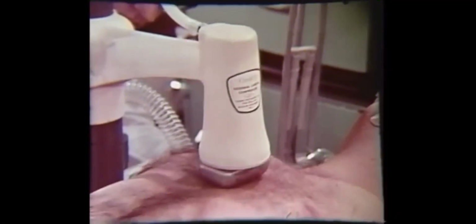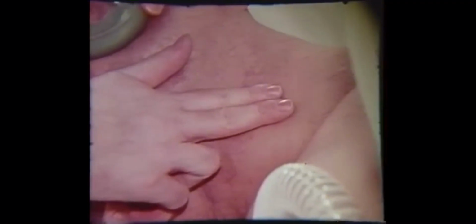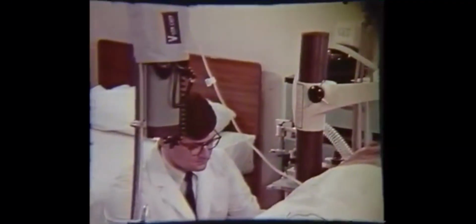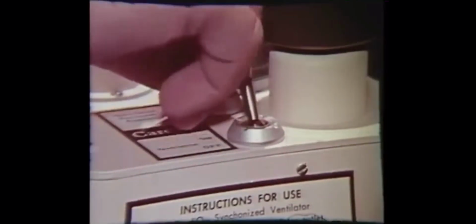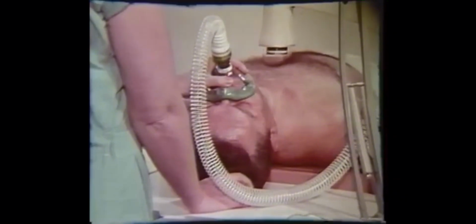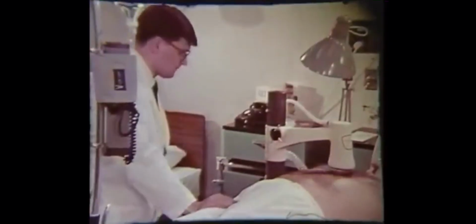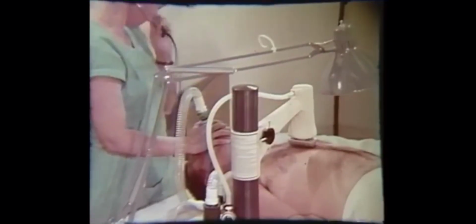The piston, which is placed on the lower half of the sternum directly in the midline, is returned by natural chest elasticity. A first check of compression effectiveness is made by palpating the carotid and femoral pulse. Turn the ventilator switch on. The pressure-limited synchronized ventilator automatically ventilates the patient during a brief diastolic delay after every 5 cardiac compressions. The ventilator will also function without cardiac compression as long as the compressor force gauge indicates at least 25 pounds of pressure. Confirm adequate air exchange by watching the rise and fall of the chest and with the stethoscope.